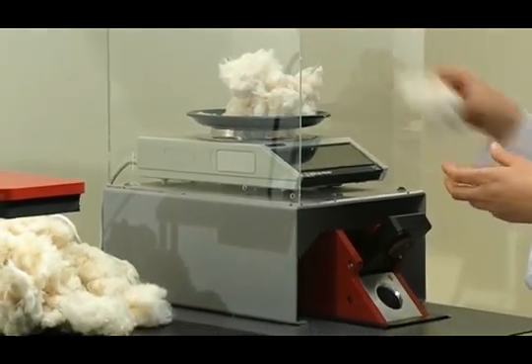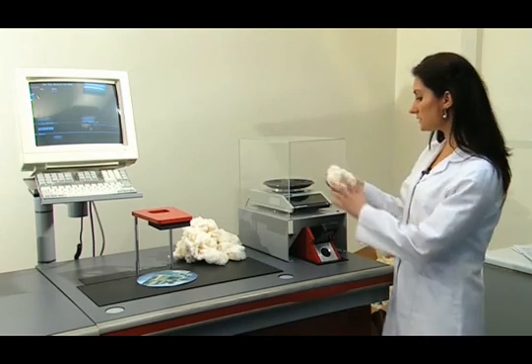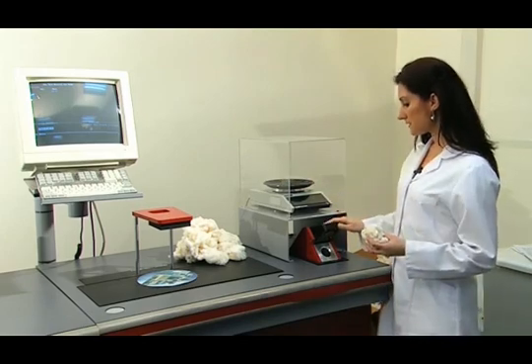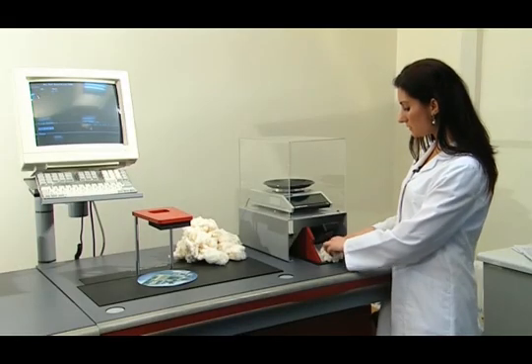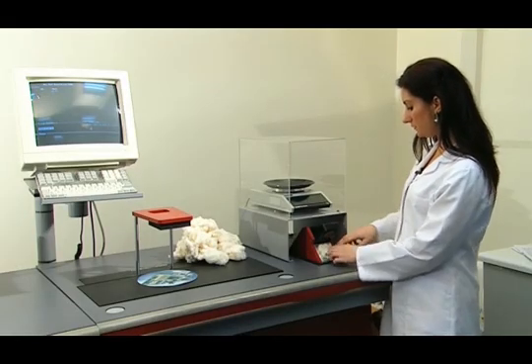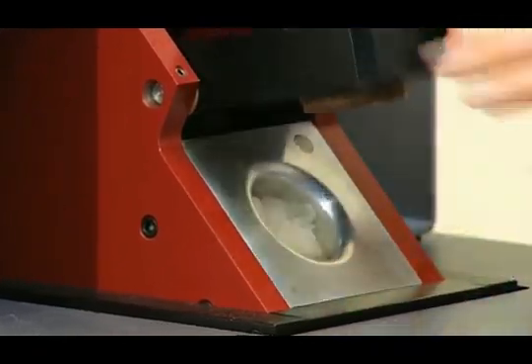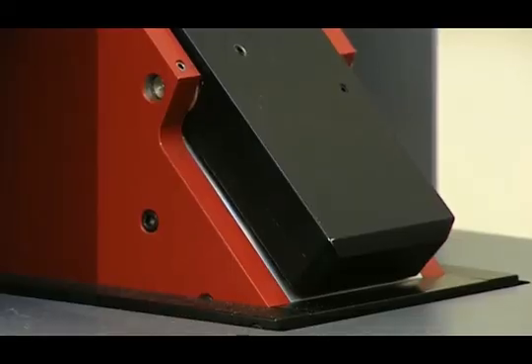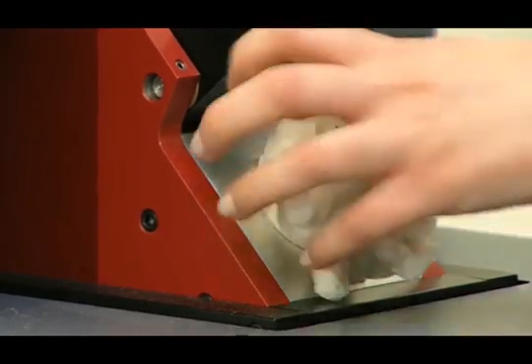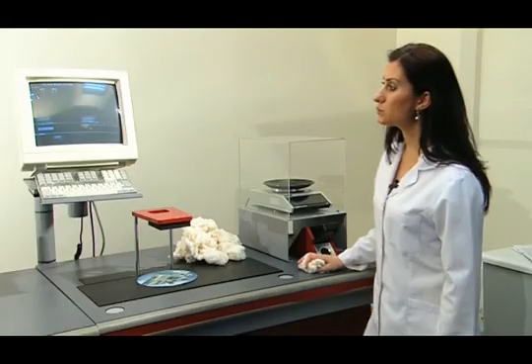After the weighing process, the sample is taken and placed into the sample chamber. At this time, 6 to 6.5 bars of air flow is passing through. The lid of the device will automatically be opened after the air flow has passed through the fibers of the cotton. After this operation has been completed, we can read the micronaire value on our device's computer.